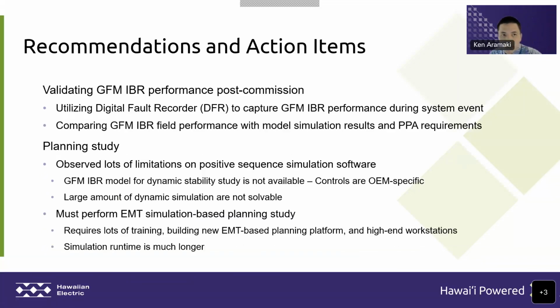Okay, and while grid forming is shown to be supportive in the simulations, we need to be able to confirm that the performance is actually meeting what the models show. So we're going to continue to utilize digital fault recorders to capture the performance of the grid forming IBRs during system events, and use that information to calibrate our models and simulations for the future. And while the simulations are not perfect, they still provide a peek into what that future performance is going to look like for these plants.